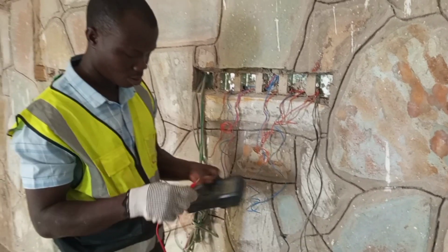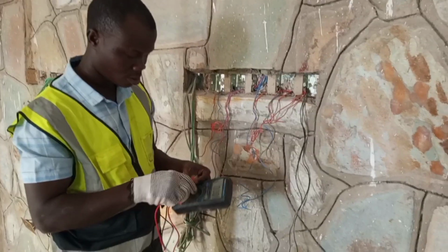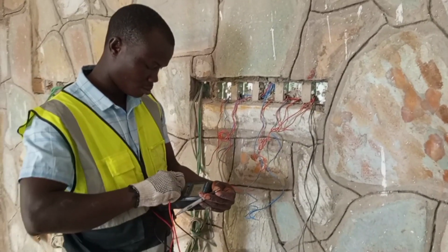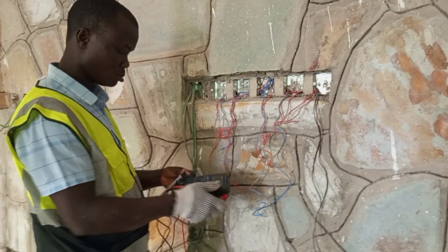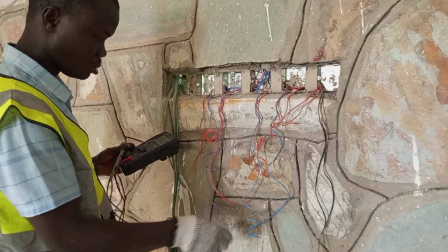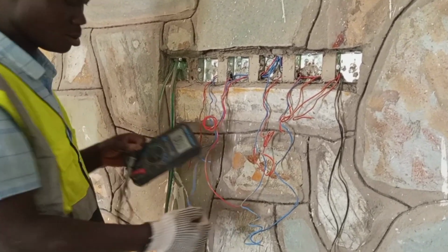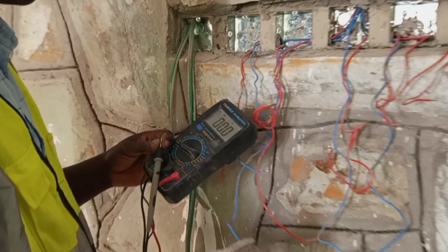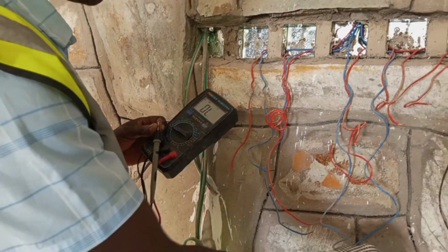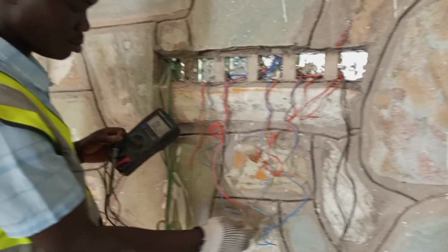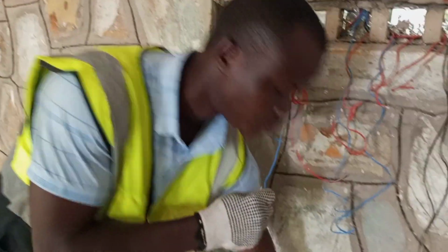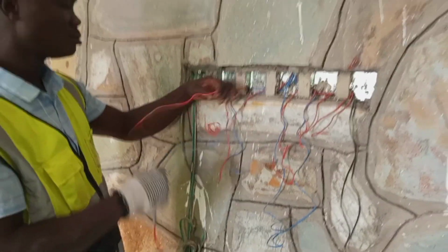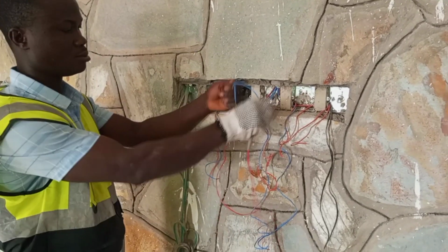So there is a switch wire that is intended for a particular light, but at the end of the day, after the POP or after the ceiling, the positions of those switch wires can change. So at the time that you are going to do your final connection of the accessories, you still have to make sure that there is a feed in that switch box and there is also a switch wire that connects from the box to the very lighting point that you intend it to be. And we can check this by means of the continuity testing method.